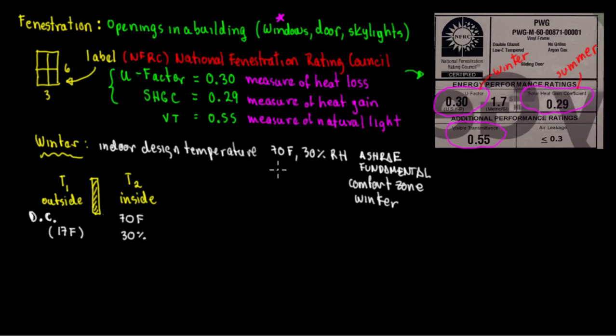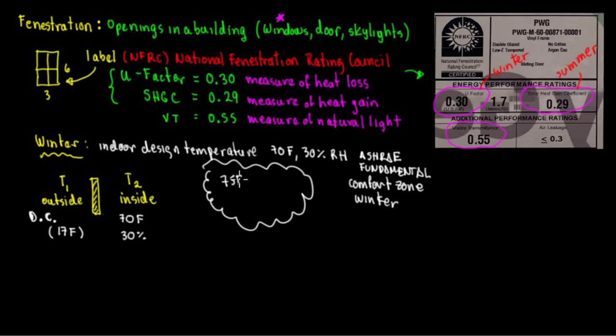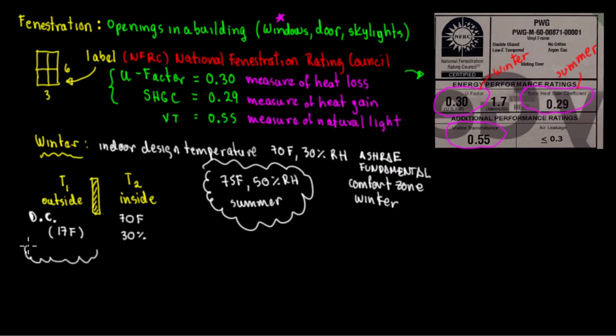In summer, instead of 70, you're going to have 75 degrees Fahrenheit and 50% relative humidity. So you have the indoor design temperature for both winter and summer, and the outside design temperature depends on the location.